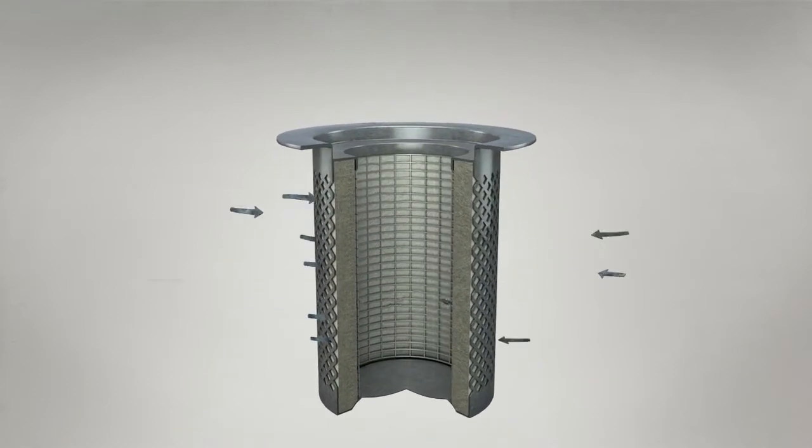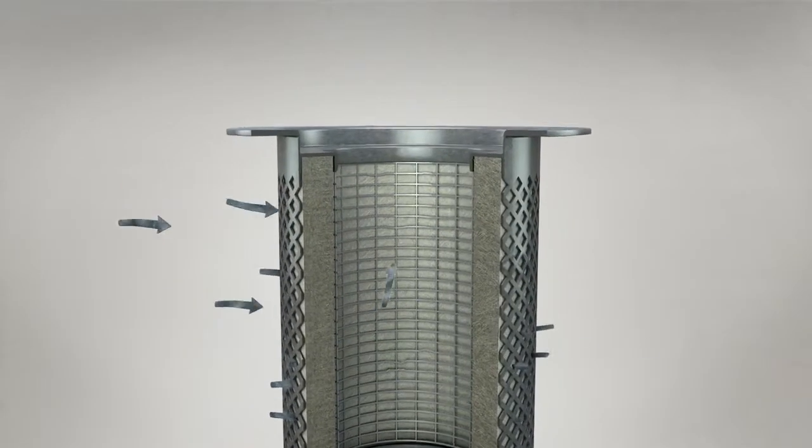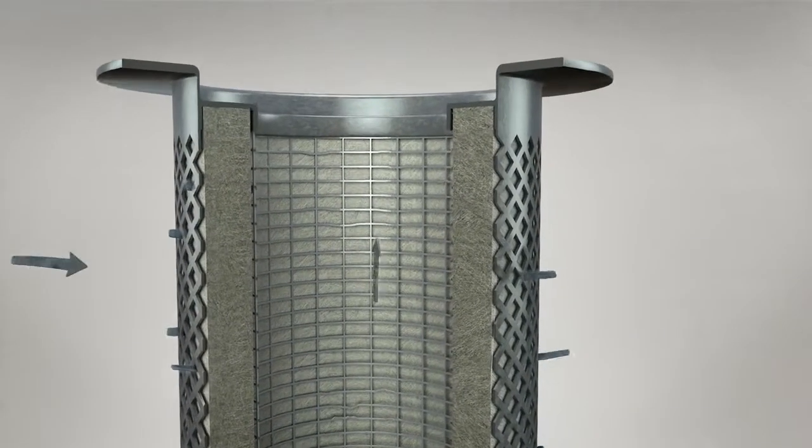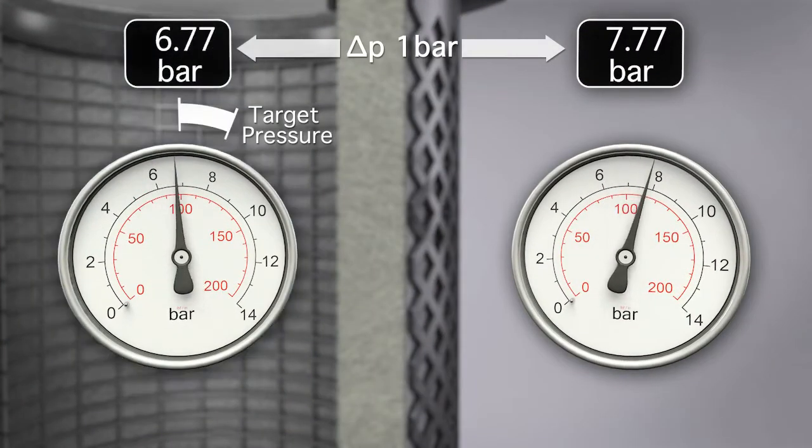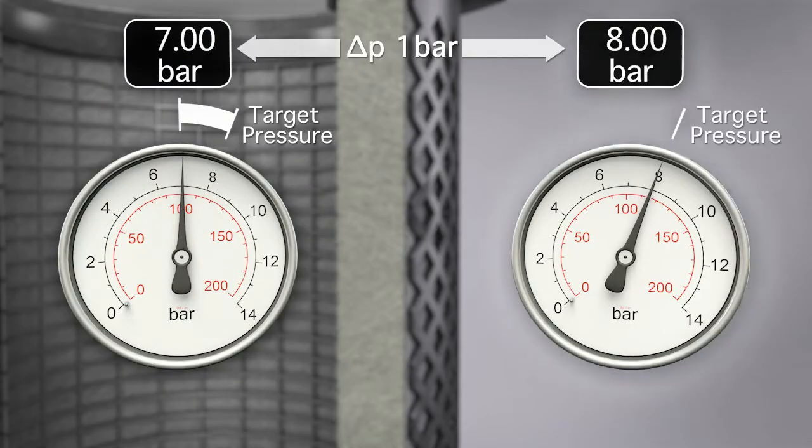Filtration media that is too dense will restrict airflow, creating an increased pressure differential across the element. Consequently, the compressor will continue to think its target pressure hasn't been reached, when in fact it has.